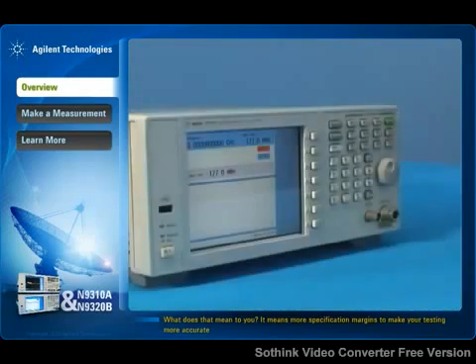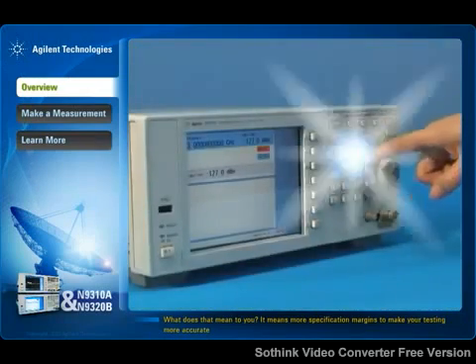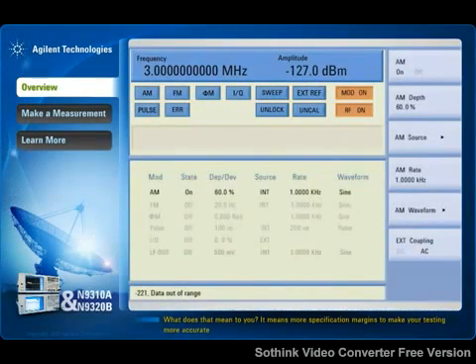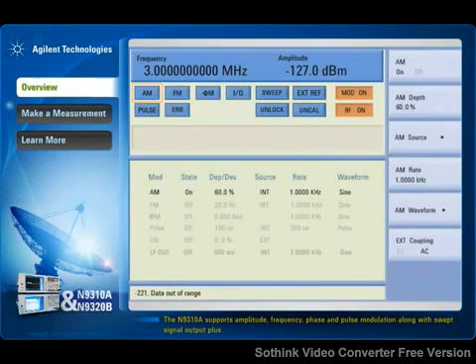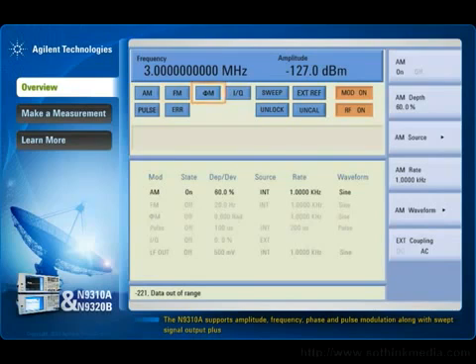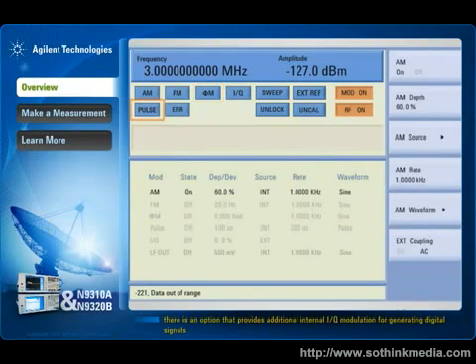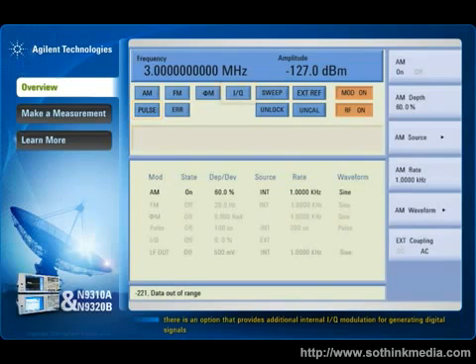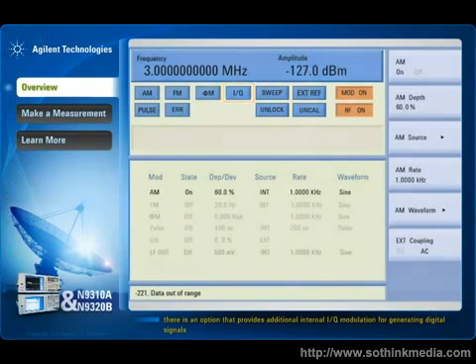What does that mean to you? It means more specification margins to make your testing more accurate. The N9310A supports amplitude, frequency, phase, and pulse modulation along with swept signal output. Plus there's an option that provides additional internal IQ modulation for generating digital signals.